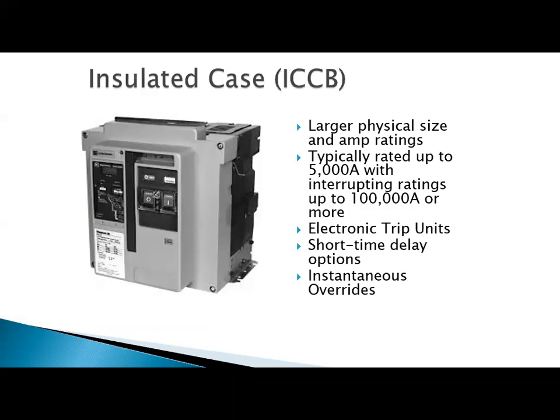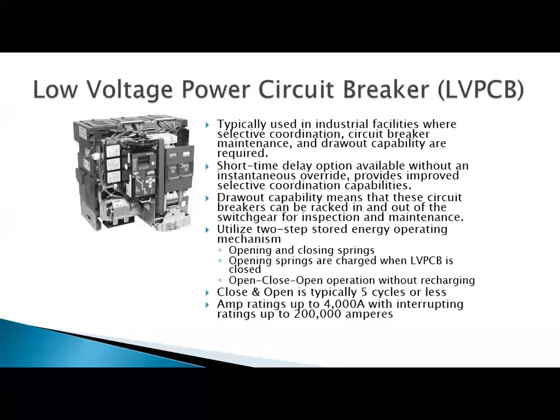And here we can see an insulated case circuit breaker. They are larger in physical size, right? They can be all the way up to 5,000 amps. We can see their interrupting ratings. We could also make adjustments on this one for a short time delay option if we had motors connected to this, or instantaneous trip. Also, a ground fault setting. And so we can set all these settings with these larger case breakers.